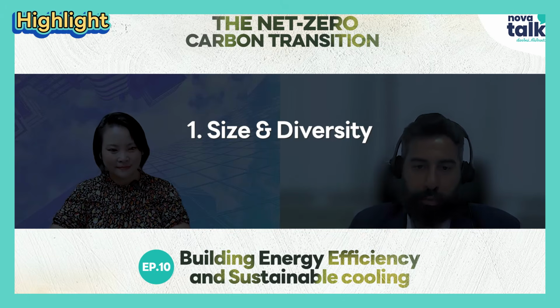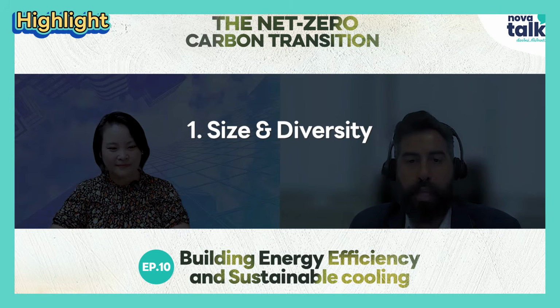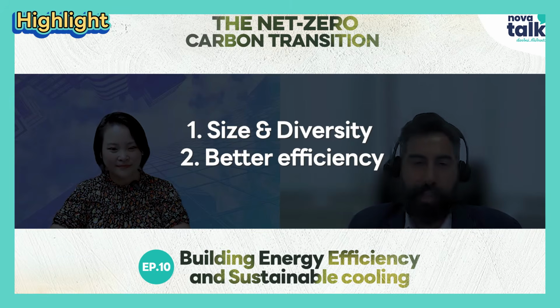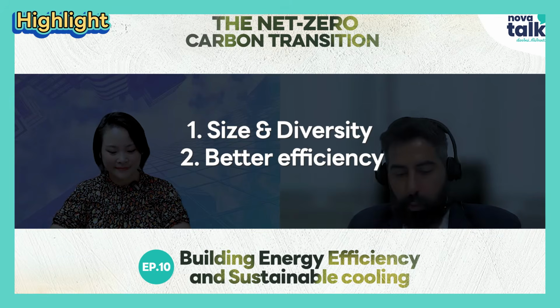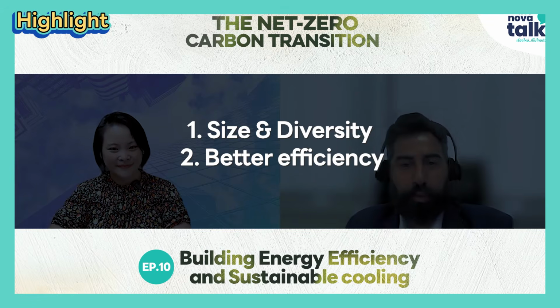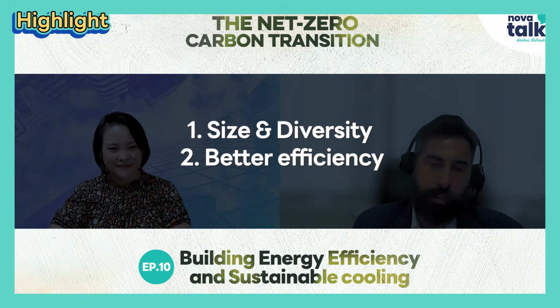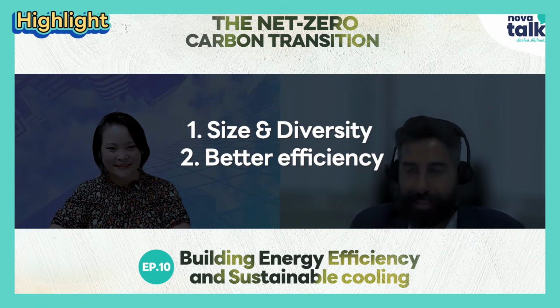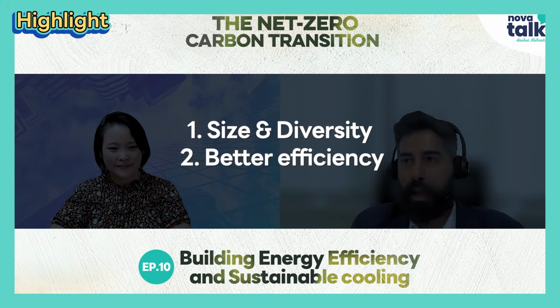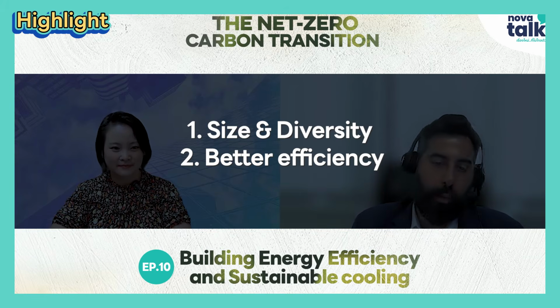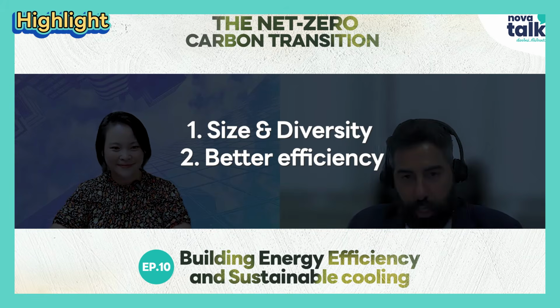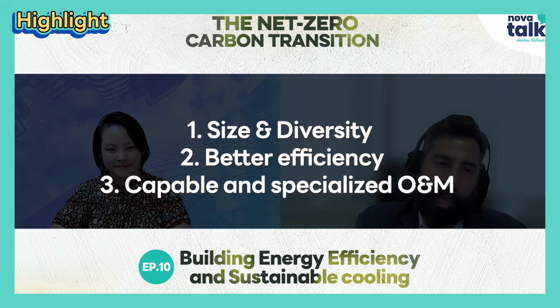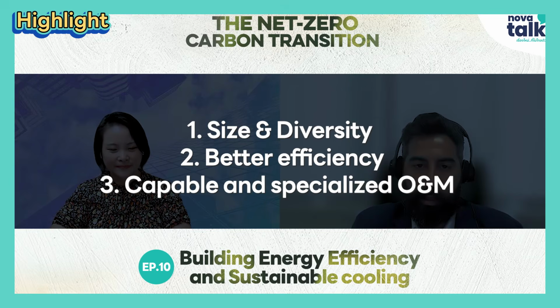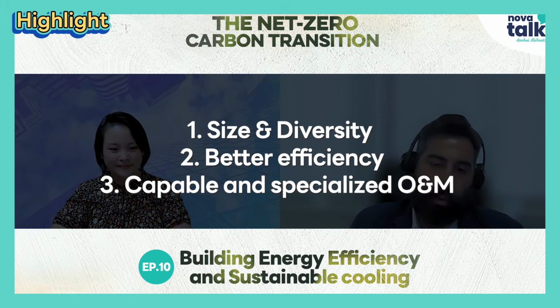If you put one central plant for all these 20 towers, you reduce your installed capacity. Second, the efficiency will be better because now you have all these tower loads together. You put a thermal storage tank as well, and you'll run your chillers much more efficiently. So there's the scale of it, the design will be better, and the operation and maintenance - since you have a capable district cooling provider with specialized teams - they would run that plant way more efficiently than these 20 separate systems.